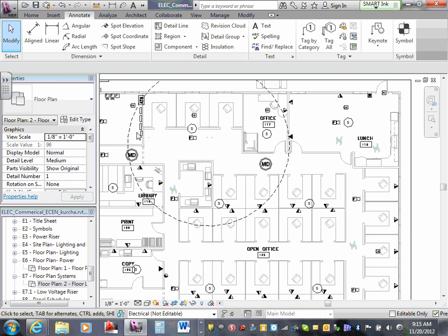Obviously, it costs more money, so contractors might not want to do that. But it's more of a best practice type of thing. And when you get into candelas, also like in the restrooms, you don't need a 110 candela strobe in there, because it's a small space, so you can put a 15 or a 30 in there and be fine.